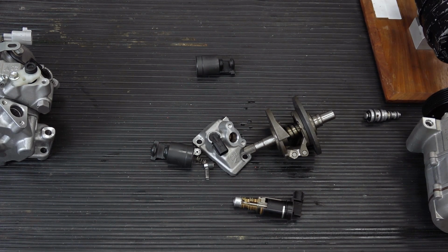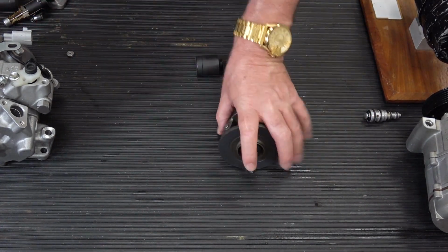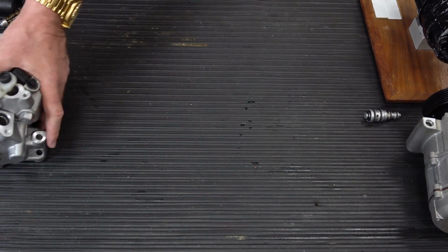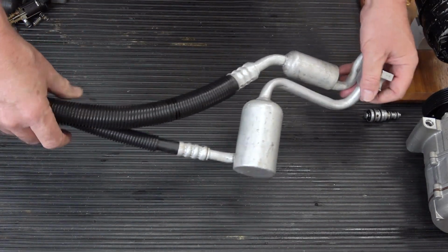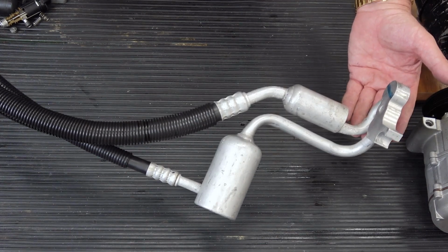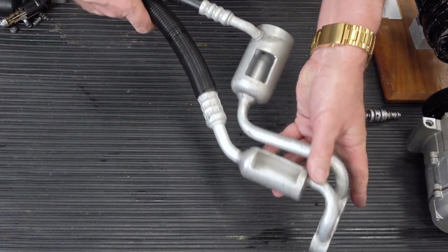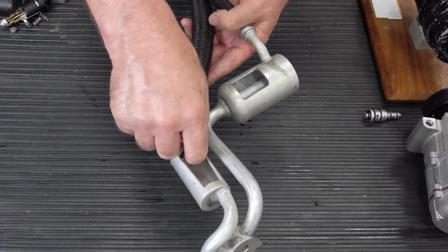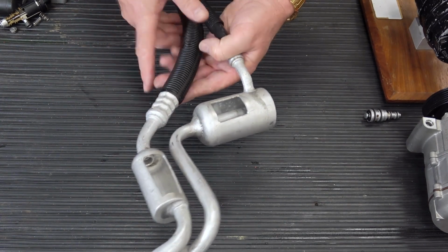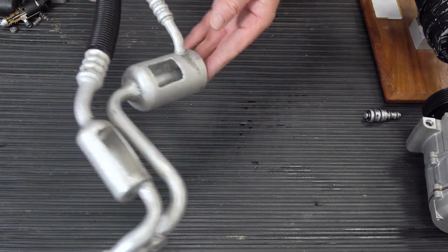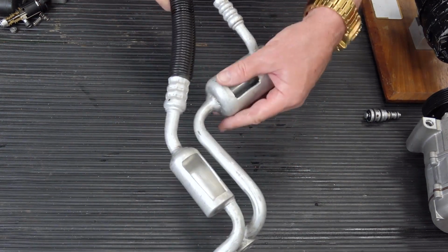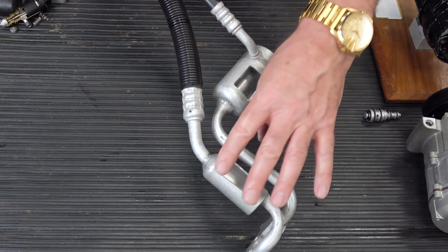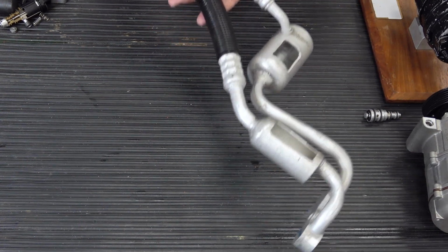I've got a couple of old hoses here that we can quickly take a look at. I will just move my little demonstration samples out of the way. You can see here I've got an old hose assembly, and you might think, couldn't I flush these hoses? The problem with this hose assembly is these are two mufflers. This one is pretty empty inside, but on this one, as you can see, the line comes in and goes all the way hard up against the bottom of the can. If you get debris into this muffler, you aren't ever going to be able to flush it out. That's number one. If hoses, or manifold hoses, have any kind of a muffler or filter in the line, you should replace them because they cannot be satisfactorily flushed.